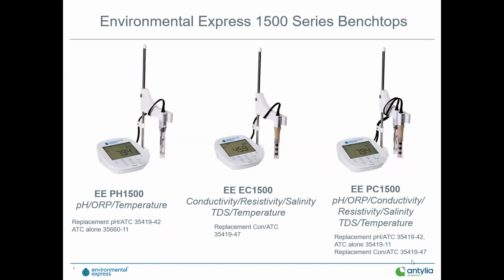So let's get into the meat of the presentation. I wanted to spend a little time initially and run through some of the options for electrodes and calibration solutions. I think that's key. The accuracy of your meter, whether it's a portable or a benchtop, is going to have two parts to it. The meter itself is very accurate. The sensor, and how that sensor is calibrated, what solution is used to calibrate it, and how many calibration points, that's really going to dictate your system accuracy, as well as the overall repeatability.